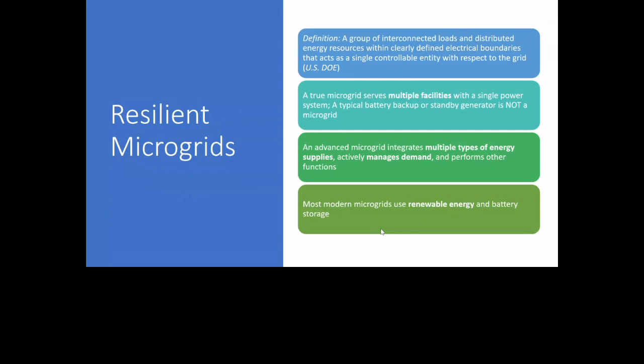We're also still connected to the utility grid, so the utility grid is now kind of a backup to our microgrid. Our first generation of power is our solar, second generation is our batteries that we store, and then if we need more energy we take from SDG&E's grid. If the SDG&E grid goes down, we island off, which means we fully disconnect from SDG&E's grid and power up our own grid through our microgrid.